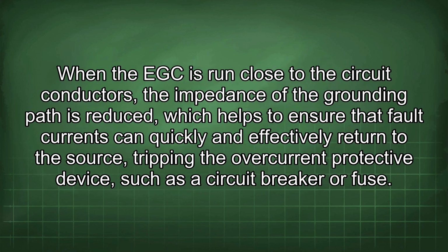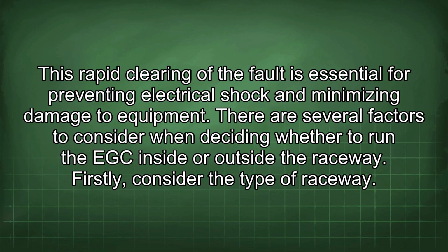When the EGC is run close to the circuit conductors, the impedance of the grounding path is reduced, which helps to ensure that fault currents can quickly and effectively return to the source, tripping the overcurrent protective device such as a circuit breaker or fuse. This rapid clearing of the fault is essential for preventing electrical shock and minimizing damage to equipment.